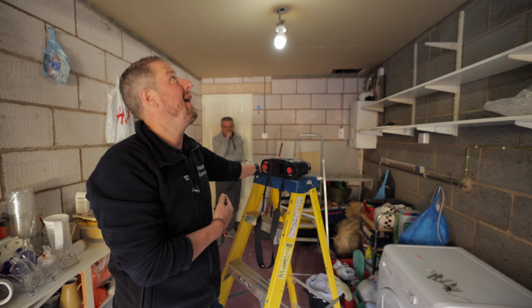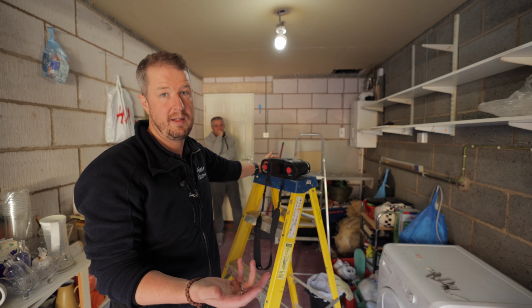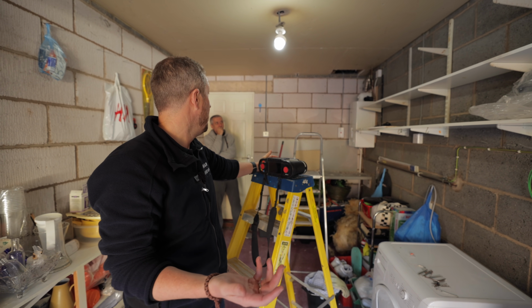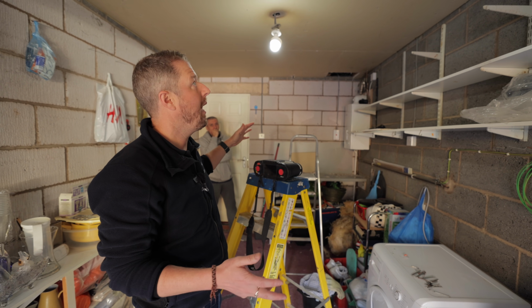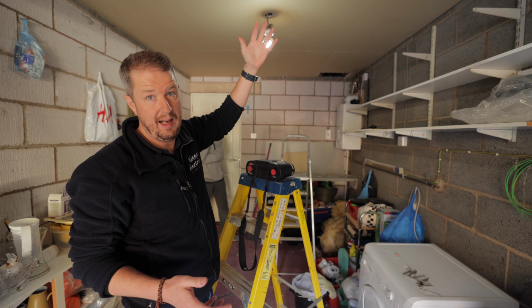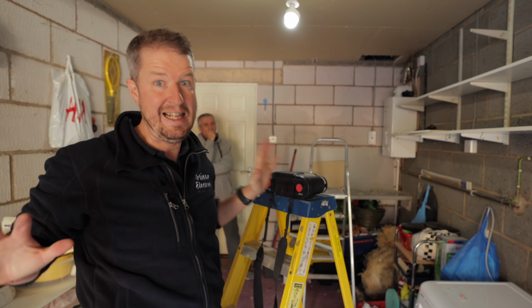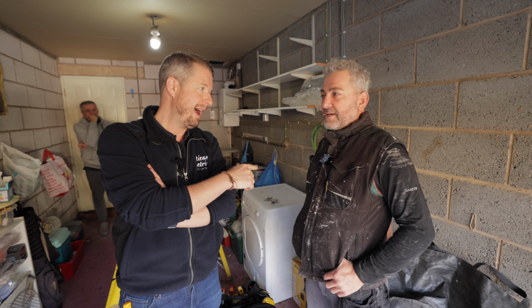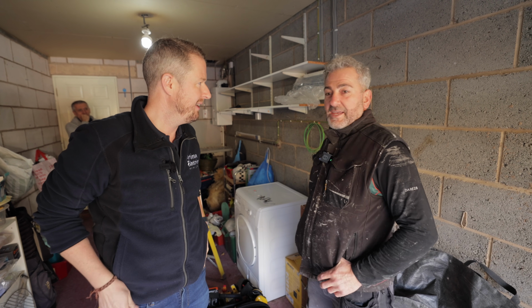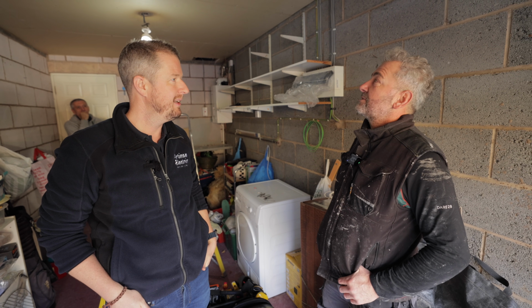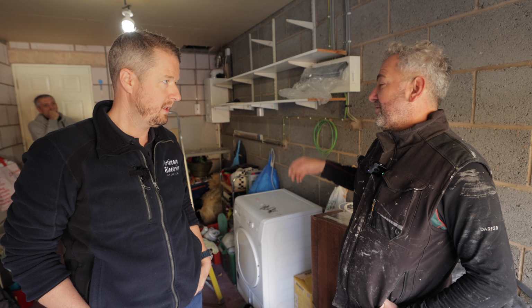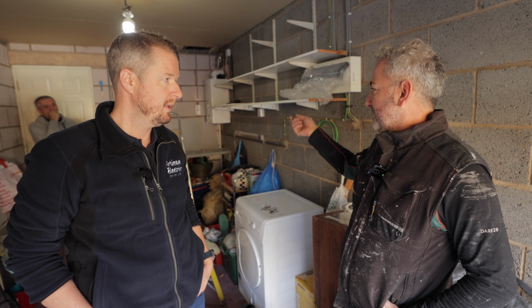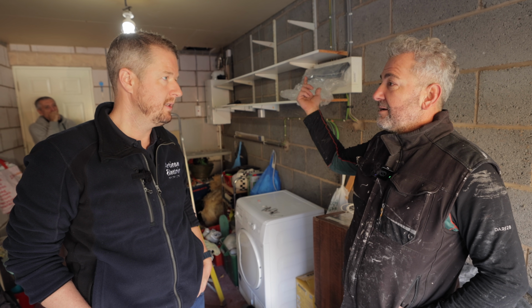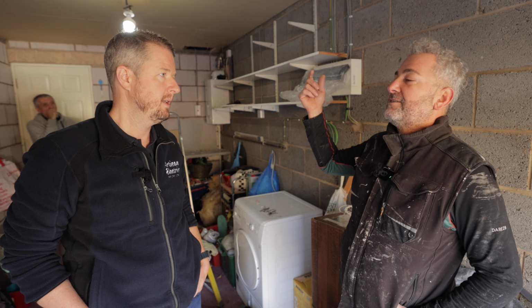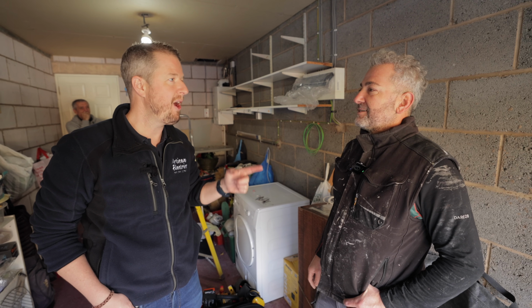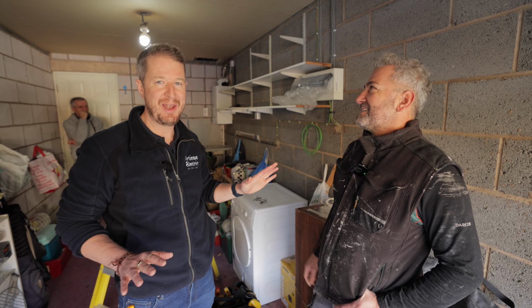So Alan's called us out here because he's having some building work done in the garage, and the builder was stripping a few things out and then noticed that the ceiling appears to be live, and obviously that's raised alarm bells. So this is Hacker the builder. Tell us what happened, Hacker. Yeah, we just started yesterday to put some new insulation on the ceiling, and then I realized my detector is touched on the ceiling, and then there's a light in there, and then I check everywhere, like the power, like electrics. Well, you did the right thing to stop the work, because you don't want anyone getting electrocuted.